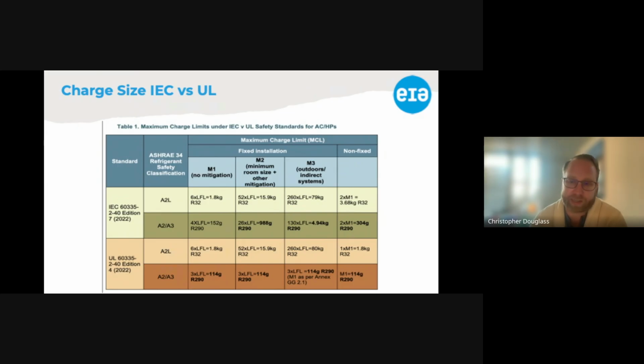The US has this capped right now at 114 grams for A3s. If you compare that to the IEC, that's almost 1 kilogram for the indoor direct systems and 5 kilograms for the outdoor indirect systems. That 114 gram cap right now makes it very difficult for any equipment to operate at any significant capacity level.